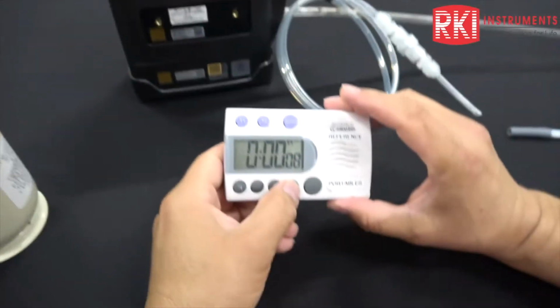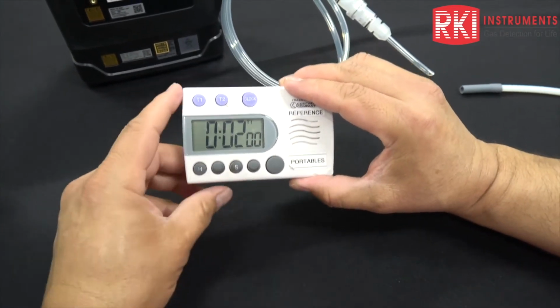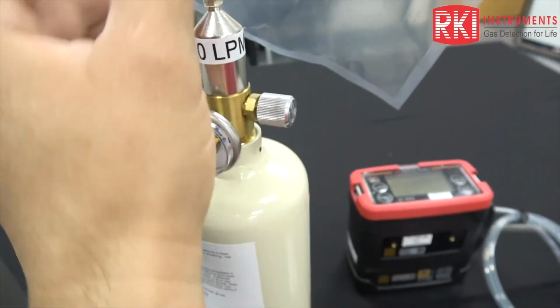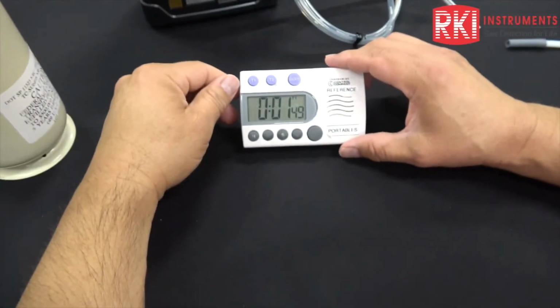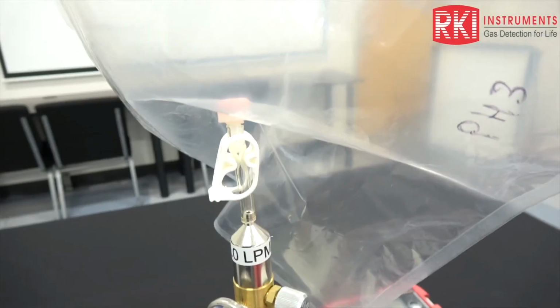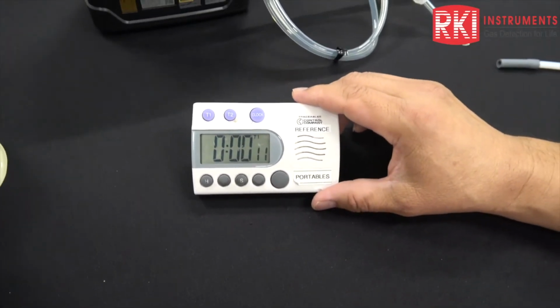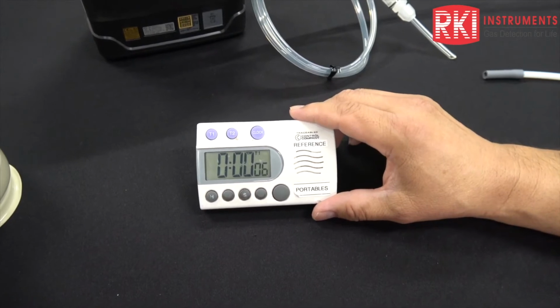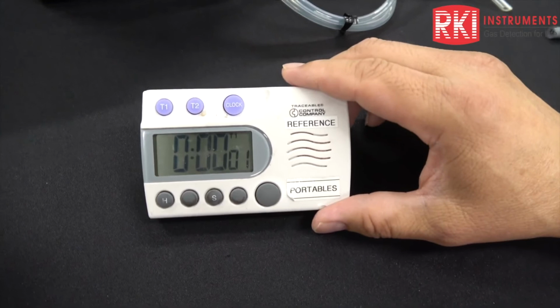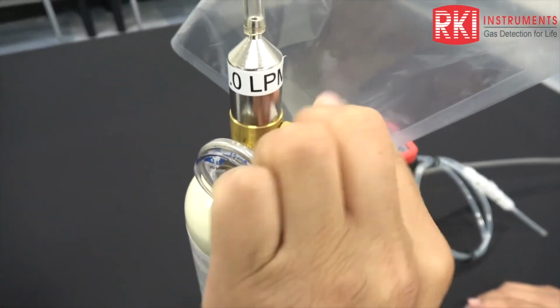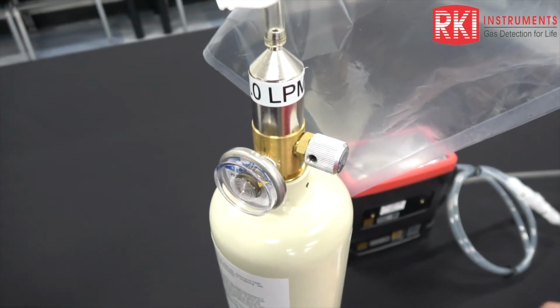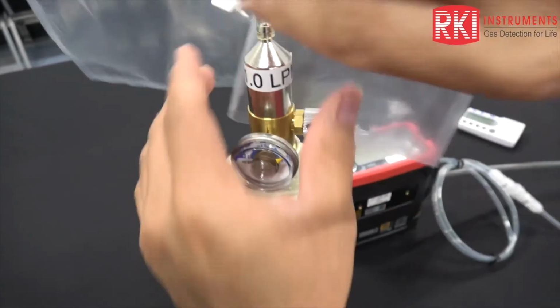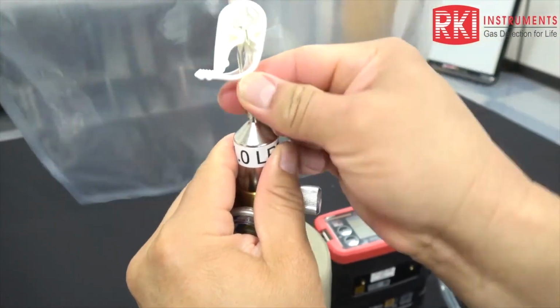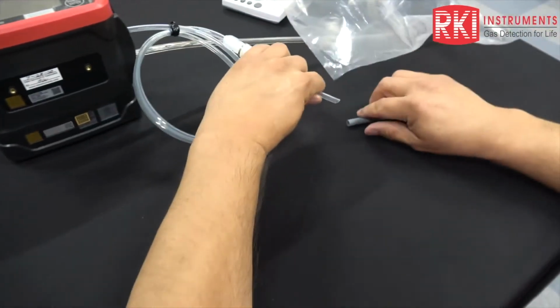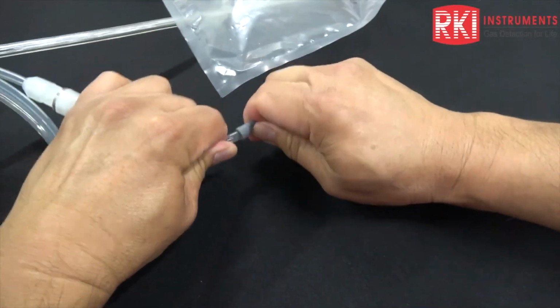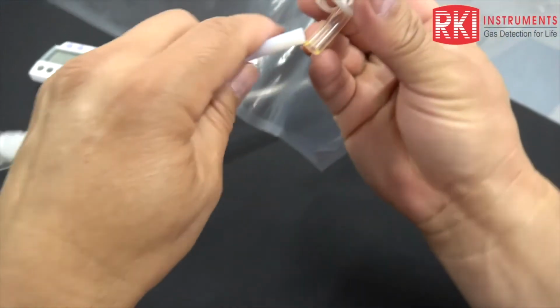Now I'm going to reset my timer here to 2 minutes. Okay, we're set there. And open up that clasp. Gas is definitely filling up the bag a little bit. Not near its capacity, but it is what we need. Okay, now I'm going to close the valve, shut the gas off. All right, then I'll close that up and take that off the barb, and then we'll put the adapter onto the end of the probe. Okay, and the other end, fill the bag.